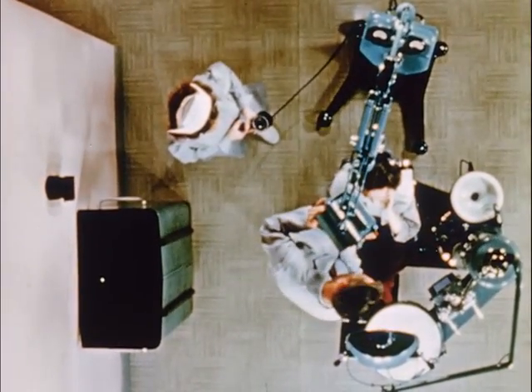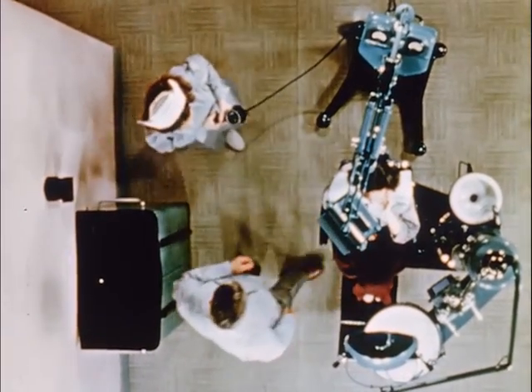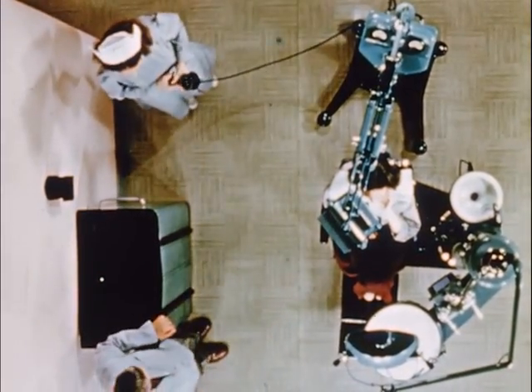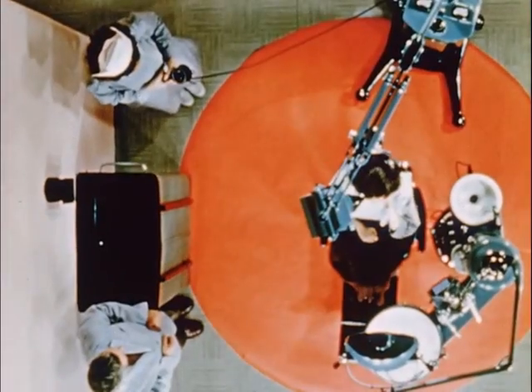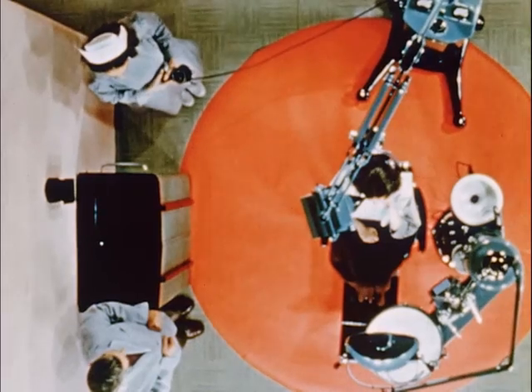To avoid exposure by the secondary or scattered radiation, which are produced about the patient and the x-ray tube during the exposure, it is necessary to stand a minimum distance of 4 feet from the patient and the x-ray tube.